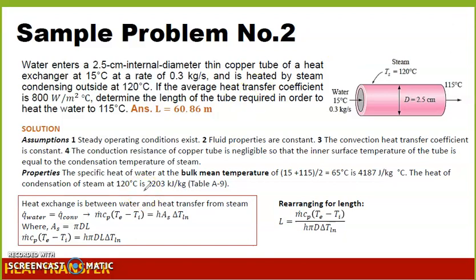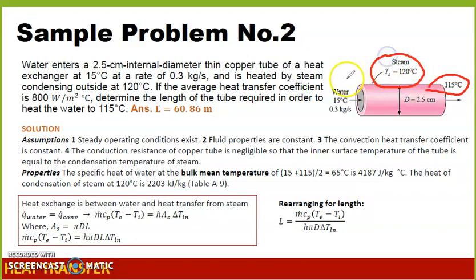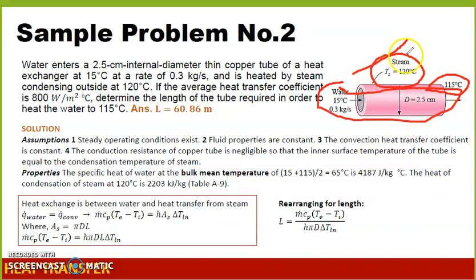Now we need to find the length of the tube required so that the exit temperature of 115 degrees Celsius is achieved. The heat coming from the steam causes the water temperature to rise. So the energy balance gives us: ṁ·CP·ΔT equals the heat convected, which is H·A_s·ΔT_LN, the logarithmic mean temperature difference.